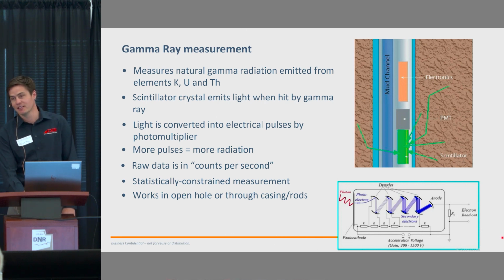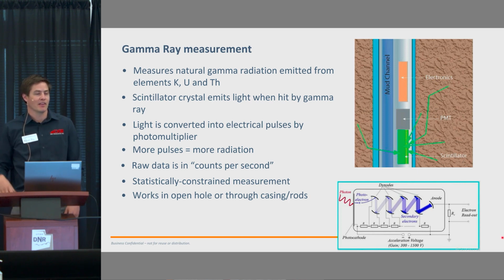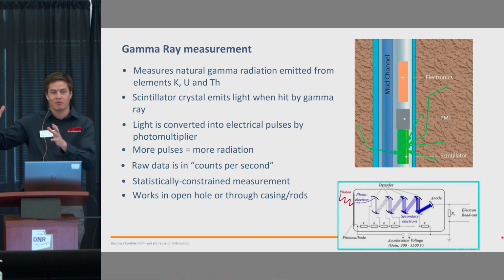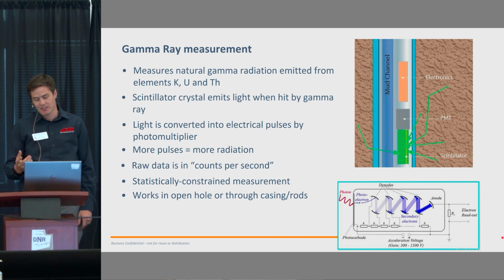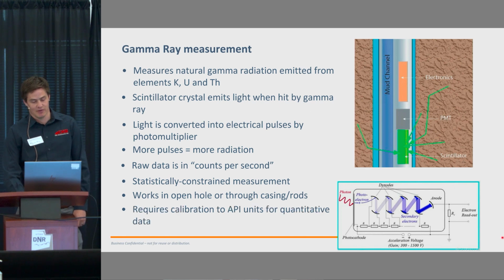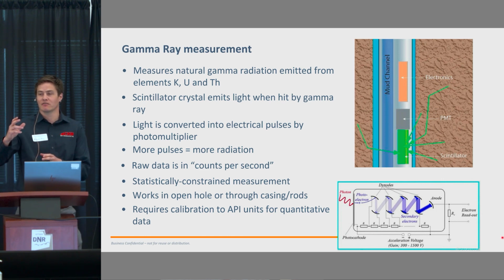One real nice thing about gamma is it works through casing, open hole, in fluid, in dry hole, because gamma rays don't care, they'll go through anything. They can get more absorbed if you have more rock, casing and cement between the probe and the formation. So you'll only get relative data if you have a bunch of cement in the way, but that can be corrected out. So gamma is pretty versatile. It works in most situations that we're going to encounter anyway. And lastly, it has to be calibrated. That scintillation crystal degrades over time, so for the same formation, a year later, it'll actually be measuring fewer counts per second.